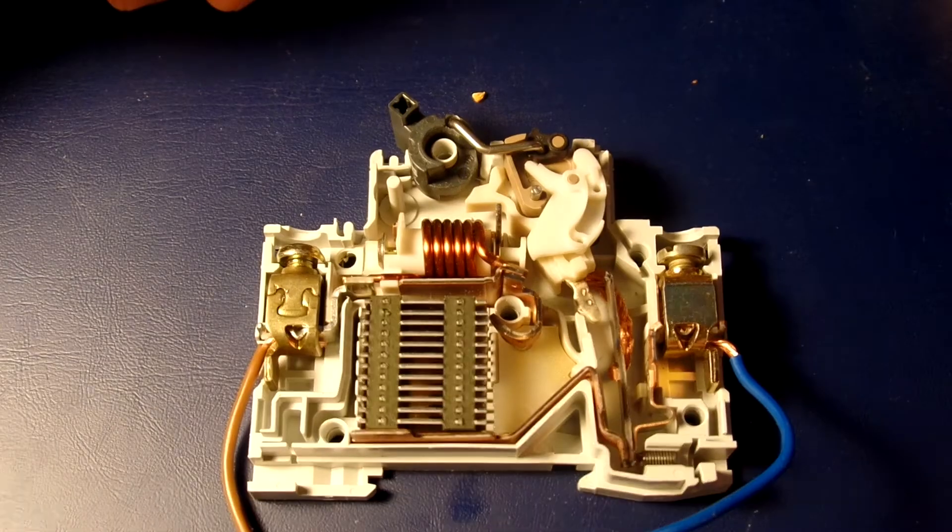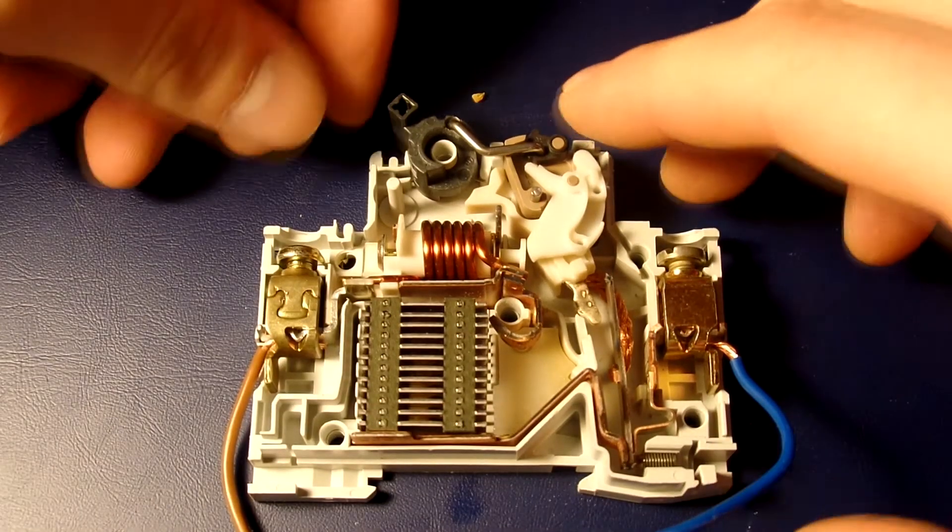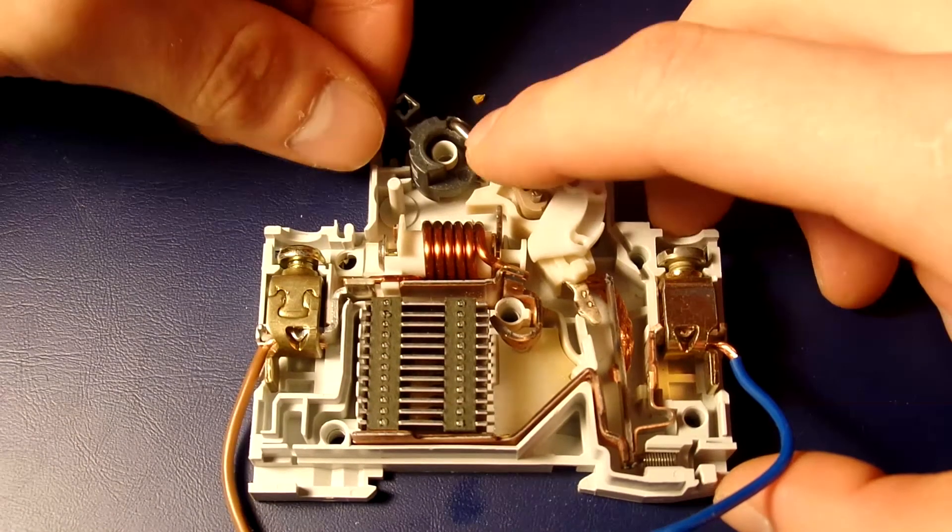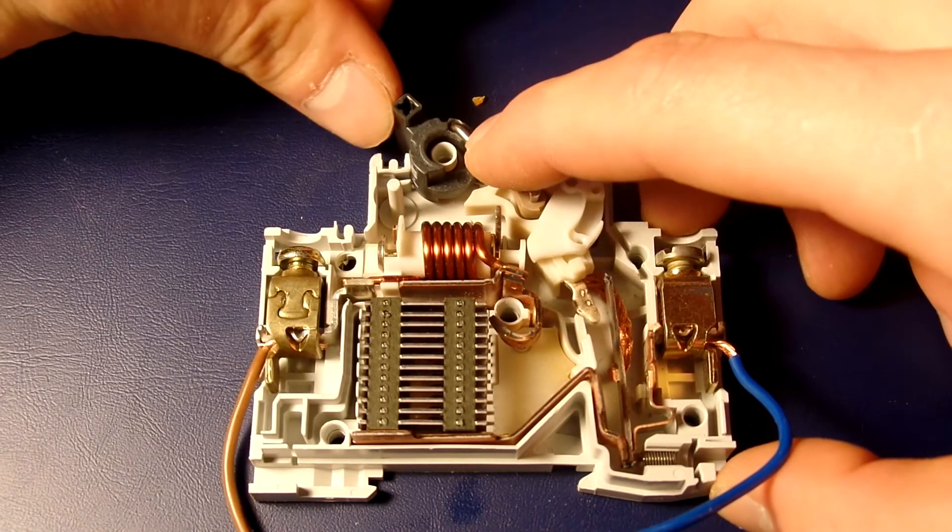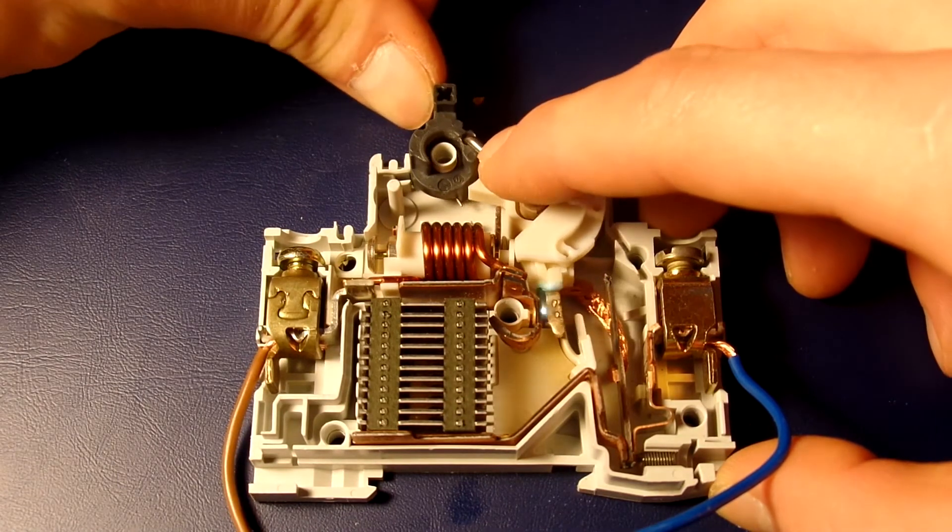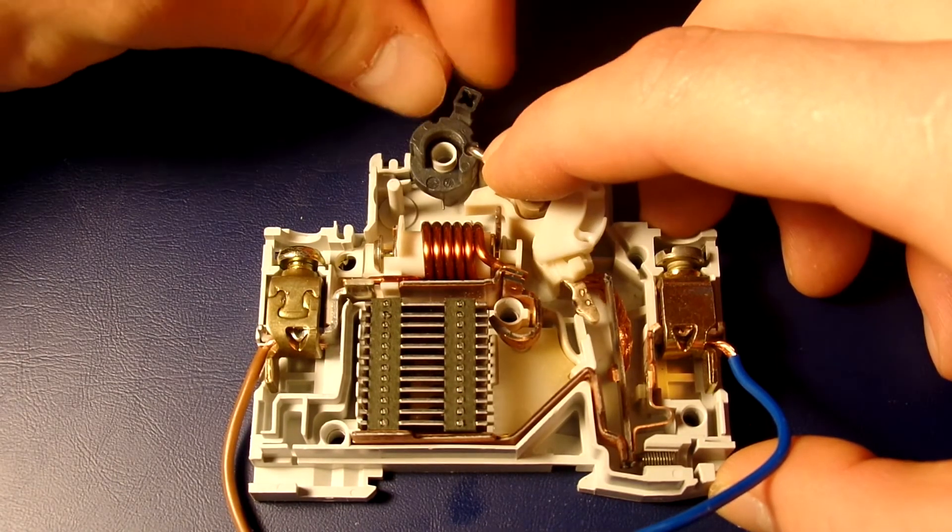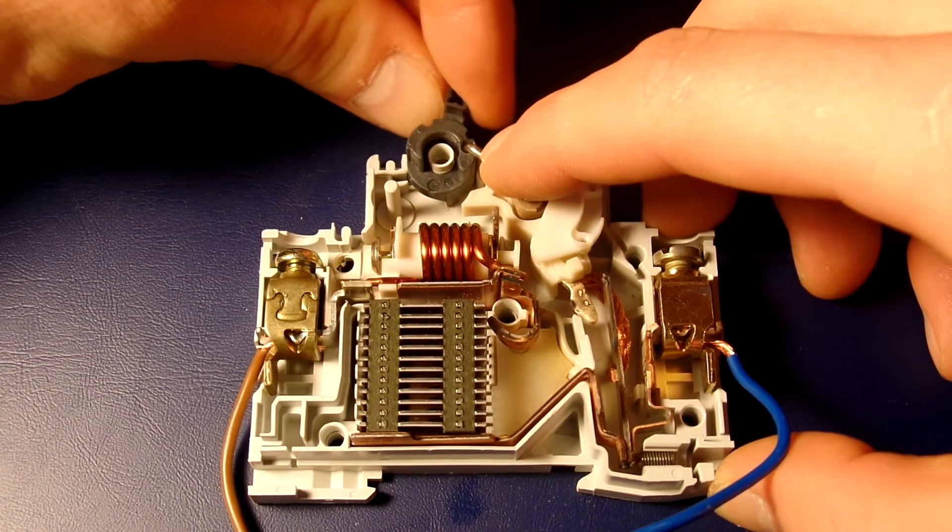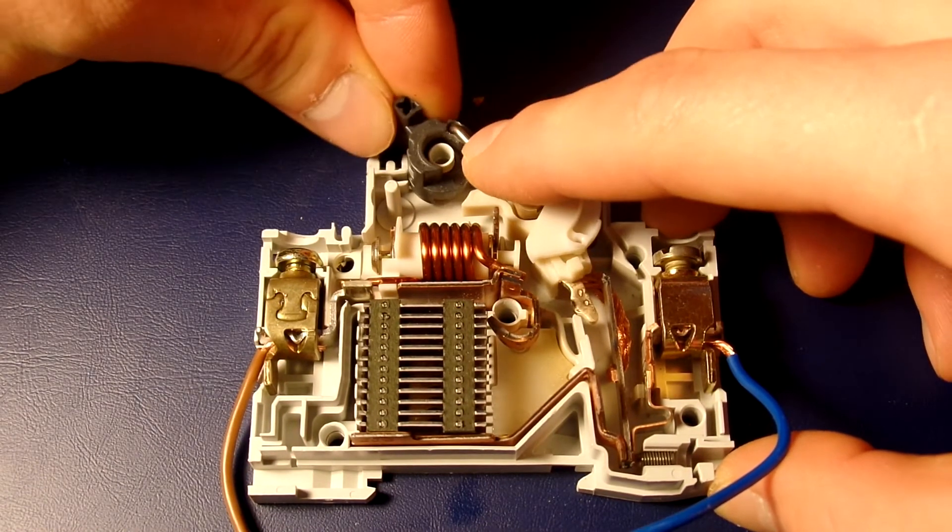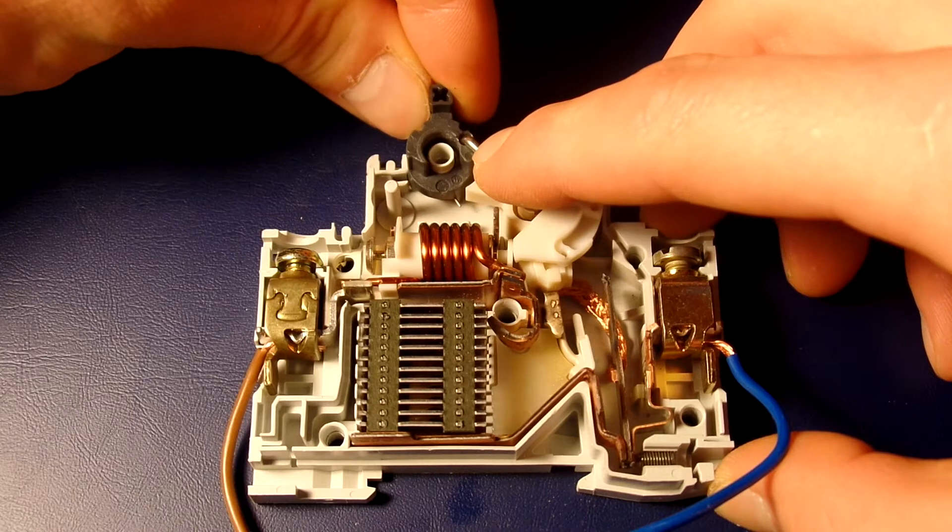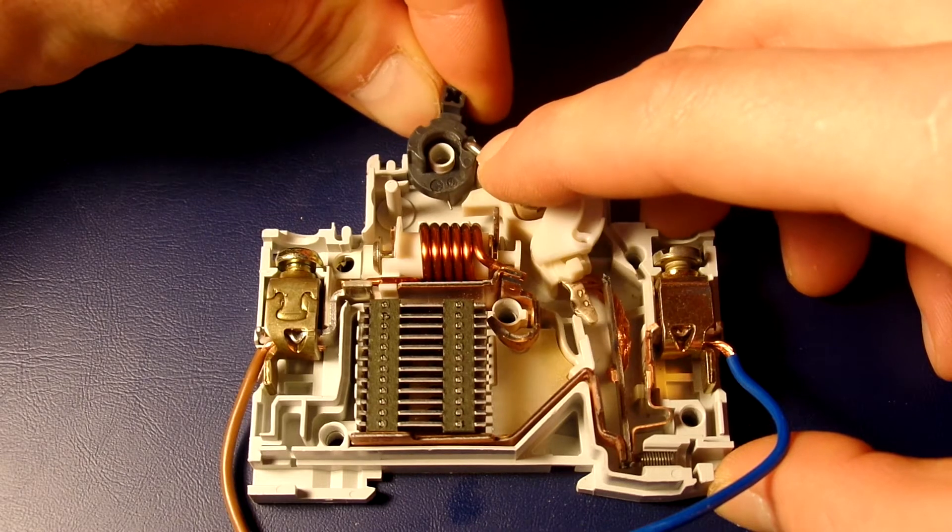This is a thermal magnetic circuit breaker. Thermal magnetic circuit breakers, which are the type found in most distribution boards, incorporate both techniques with the electromagnet responding instantaneously to large surges in current and short circuits, and the bimetallic strip responding to less extreme but longer-term overcurrent conditions.